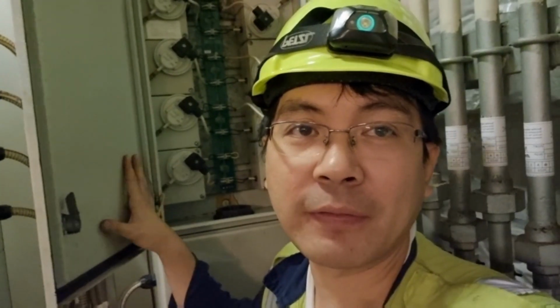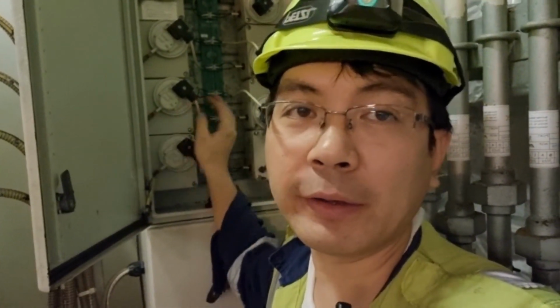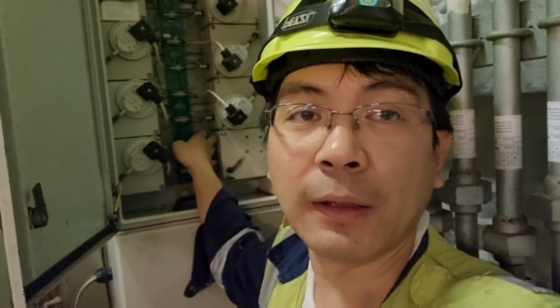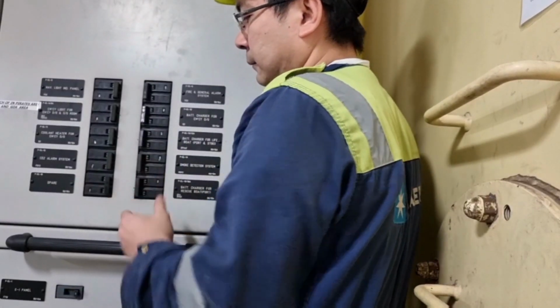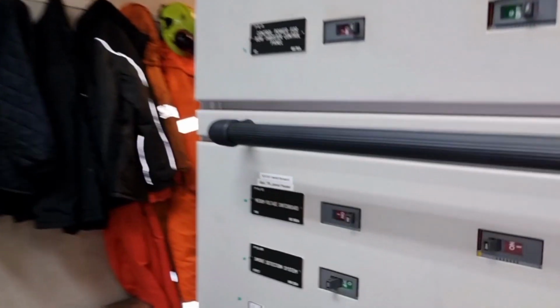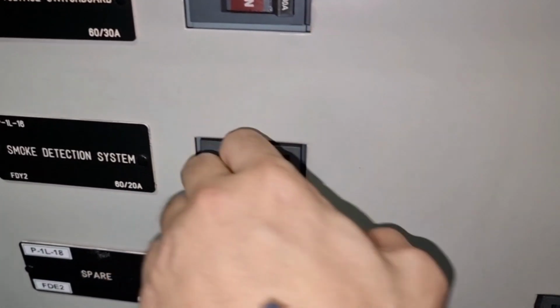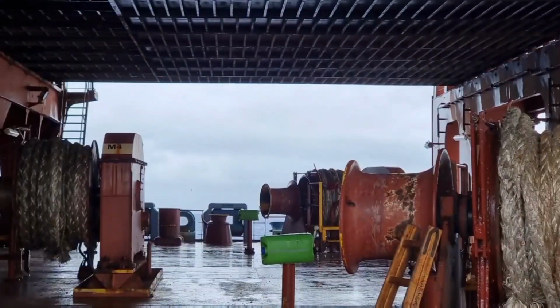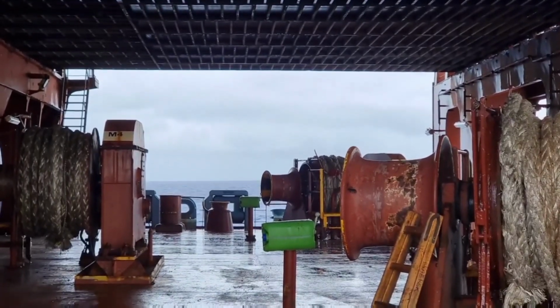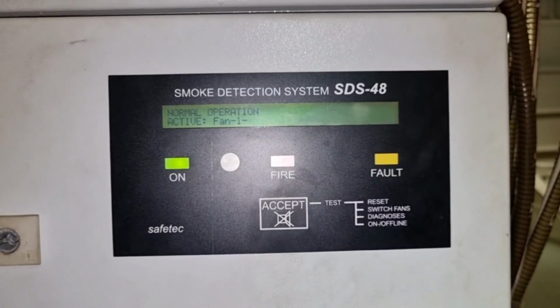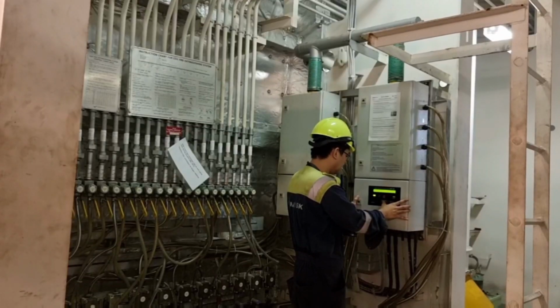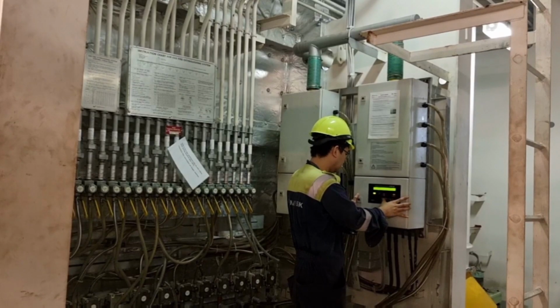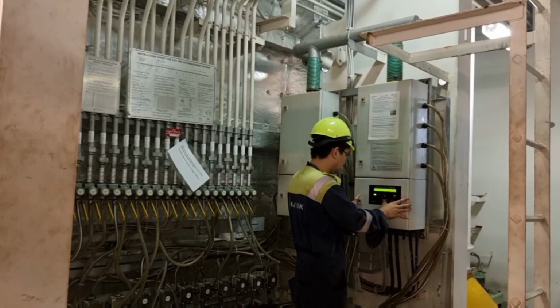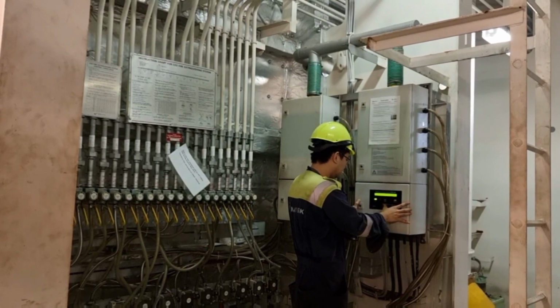After we dried up everything and the board was already in place, this PCB was also installed, and now we will power up the system and see if it will become okay. Then I went back to the emergency generator room and to the main switchboard to power on the system. After powering on, everything went in normal condition. And then my final plan is to test the system by activating one of the detectors to see if it is working fine.